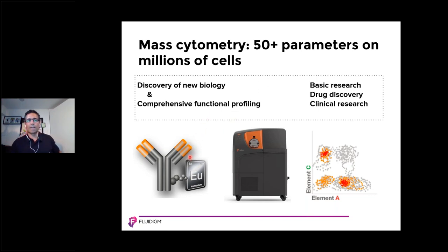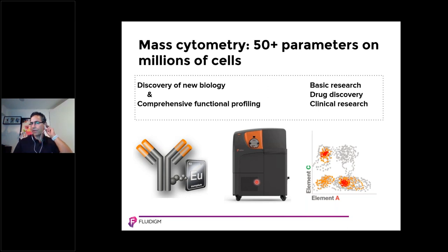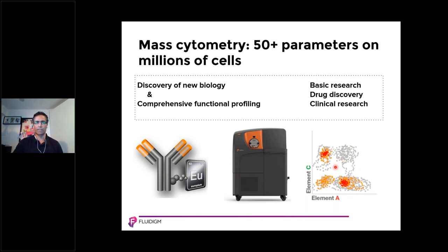This has been possible because the antibodies are now conjugated with metal isotopes instead of fluorochromes. The quantification of these metal tags is achieved with high-resolution mass spectrometry. Importantly, conjugation of antibodies with metal isotopes does not change the biology of the antibody, and the staining procedure is very similar to conventional flow. There is no need for major modification in your current protocol and workflow to label cells in suspension, so you can easily get started with mass cytometry. The data output is a conventional FCS file that can be analyzed in any third-party software that recognizes FCS files.